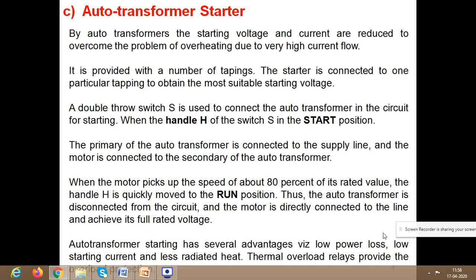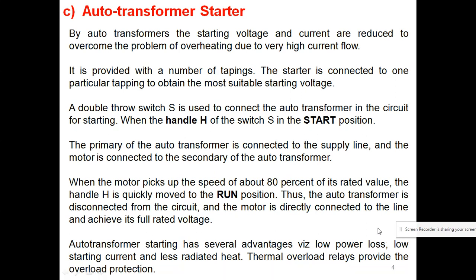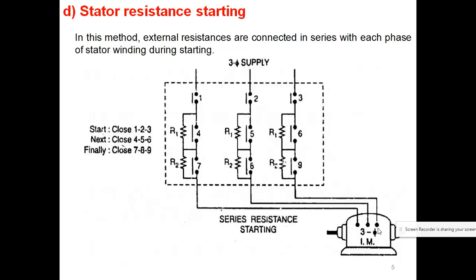The auto transformer has several advantages, like low power losses, low starting current, less radiated heat, and thermal overload relays are provided for overload protection. If we have any problem related to overload protection, then we will use thermal overload relays. So this is all about the auto transformer starter.